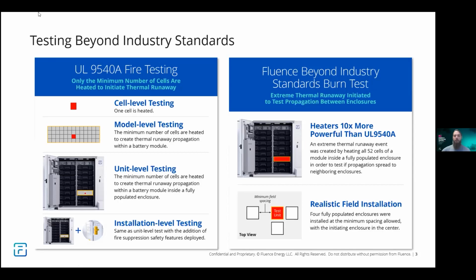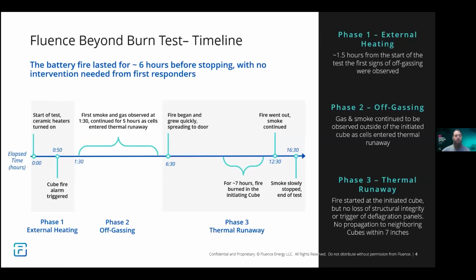For the test we conducted back in July, it took about an hour and a half for us to heat up and start reaching those first cell venting temperatures. Our fire alarm went off and reacted, and the notification system worked as designed and planned — all well before any further event would have kicked off, which would have given first responders plenty of time to show up on site and react as necessary. The second phase of the incident was the off-gassing phase.